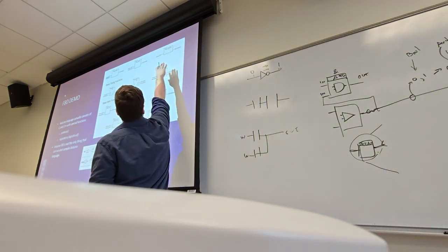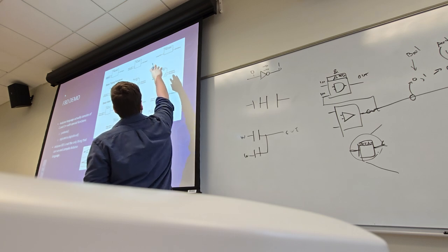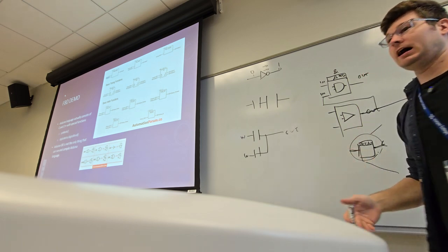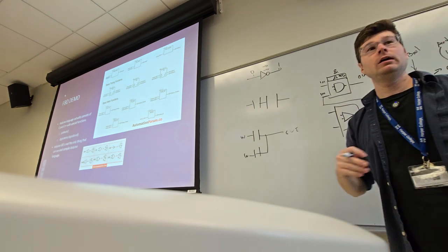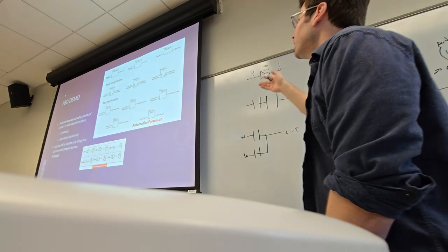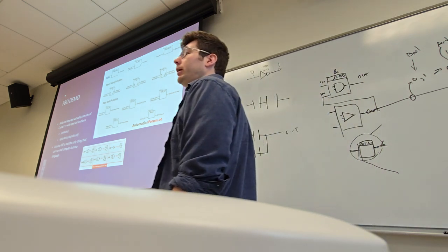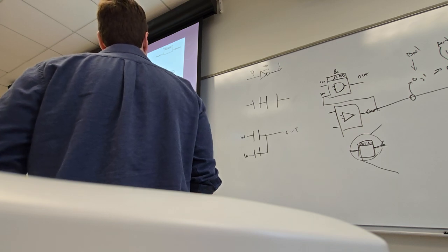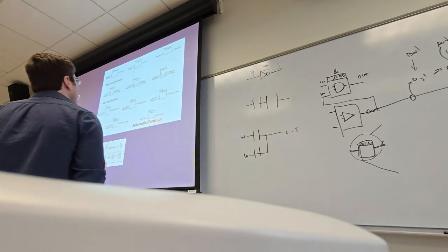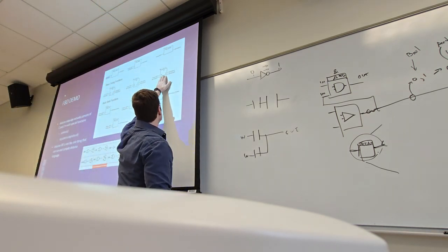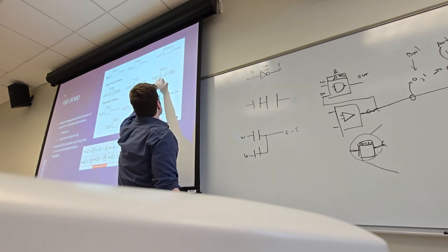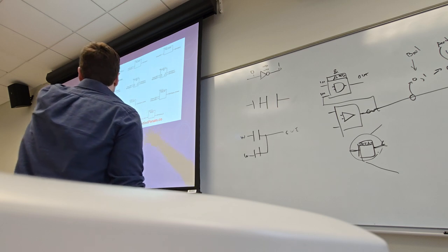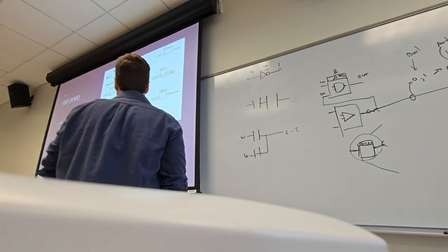In function block diagram, we also have a block that does that, okay? So if we have the wrong output, if whatever is happening on our PLC is the opposite of what we want to happen, we could just throw a NOT block on there and bang on, we're right as rain. It suddenly has the exact right output. Very useful. TP, I believe, is a pulse. So at the end of that elapsed time, it'll set a pulse. It's useful for setting things with our RS or SR blocks.